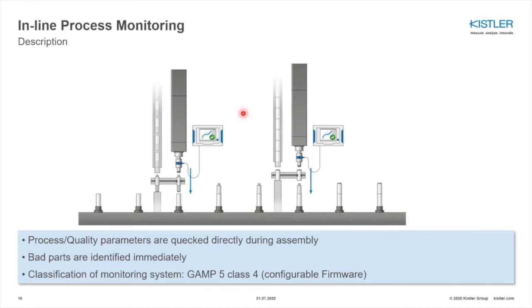But just measuring the force, one could not recognize if, for example, a part is jammed and therefore the required force is reached even when the part is not in the correct position. Regarding the requirements and application, tolerance windows, so-called evaluation objects, can be placed around the measured curves for direct tolerance evaluation.